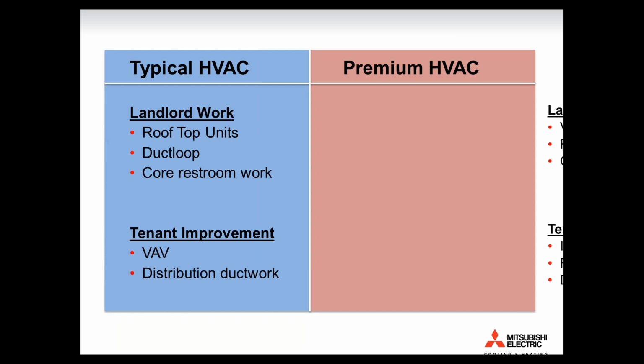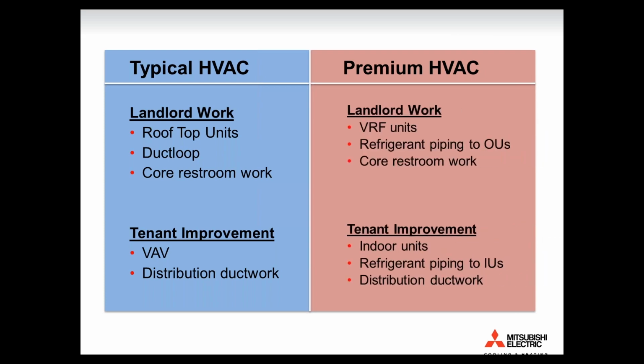So a typical solution would be VAV rooftop units with duct loops for future tenant build-out. Provide enough VAVs for temporary conditioning of the space and the entry, as well as the restroom core work for the landlord portion of the work. A premium solution would be to choose VRF as a viable option. You can provide the outdoor units, branch controllers, and refrigeration piping for the outdoor units, as well as a minimum number of indoor units to provide temporary conditioning of the building until TI build-outs occur. And TI is just my acronym for tenant improvement work. Tenant build-out would be the remaining indoor units, refrigeration piping, ductwork, diffusers, and controls for those indoor units.